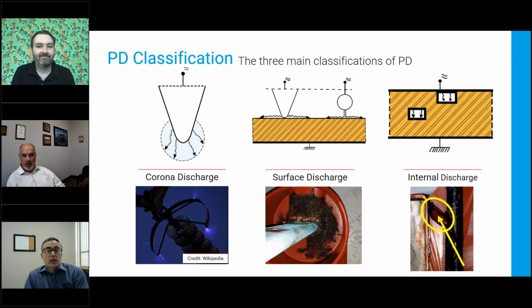You also have that rust with surface partial discharge, and you can see in that little photo there, there's rust in the treeing and tracking that you might have, for those of you that have seen it before, might recognize. Surface partial discharge is the most common type of PD, and that's one of the areas that we're going to be talking about today. There is another type, or internal or void type discharge. That is an air bubble that's inside a solid piece of insulation. It could be a resin, like it's shown in the picture there, or it could be a porcelain insulator or some type of composite insulator where you have some delamination occurring due to thermal stresses or some other issue, and an air bubble is forming.